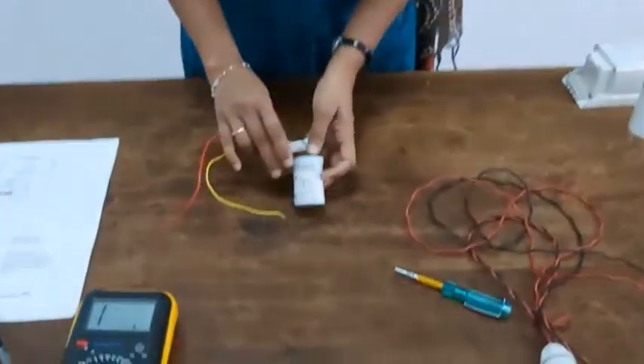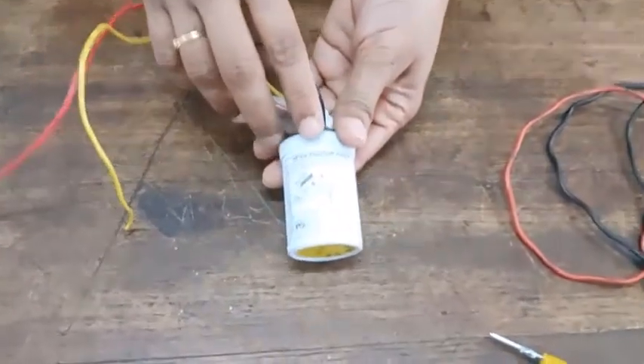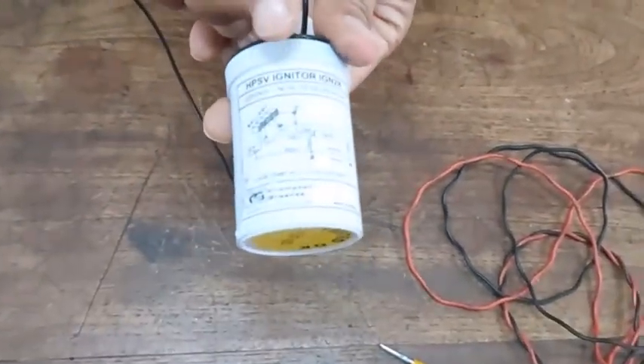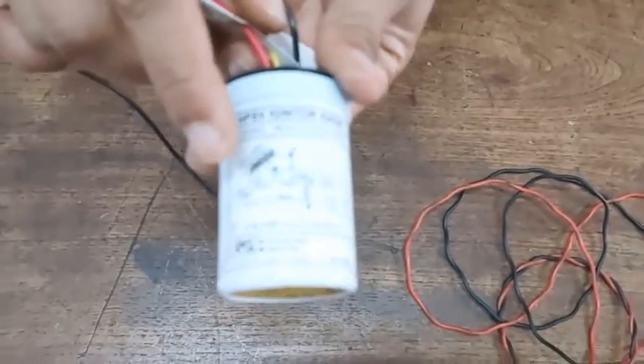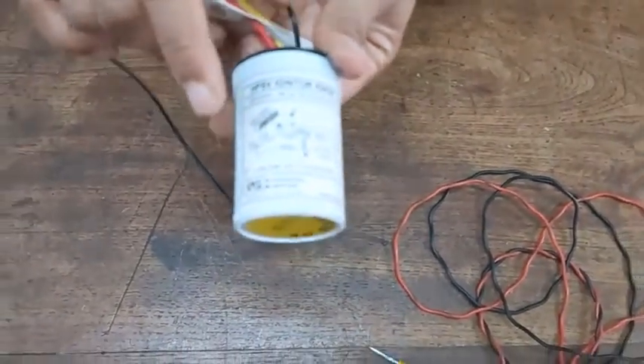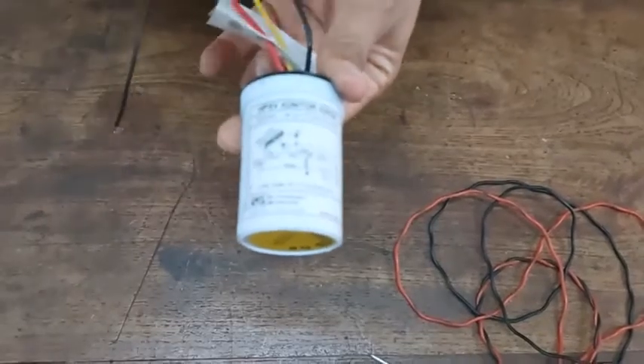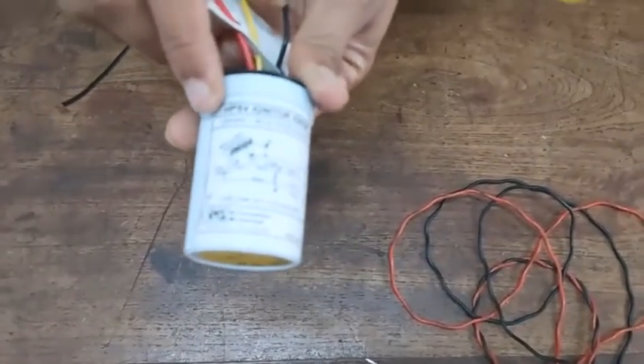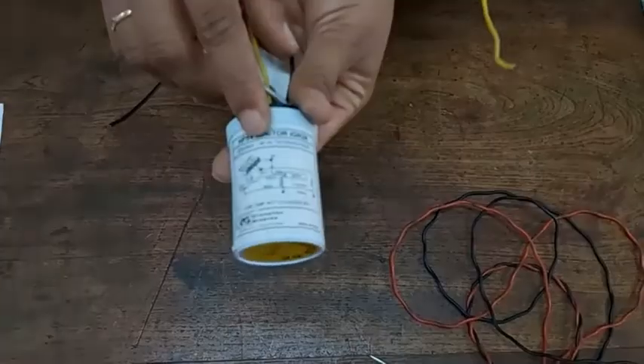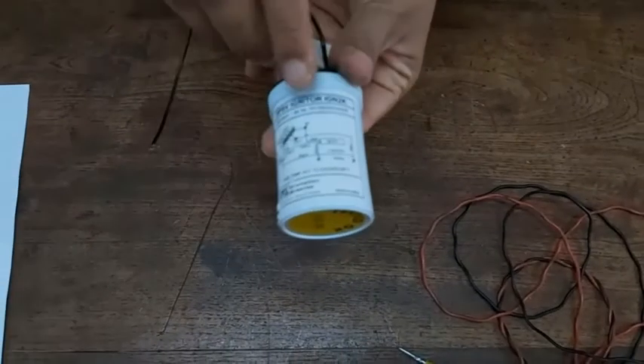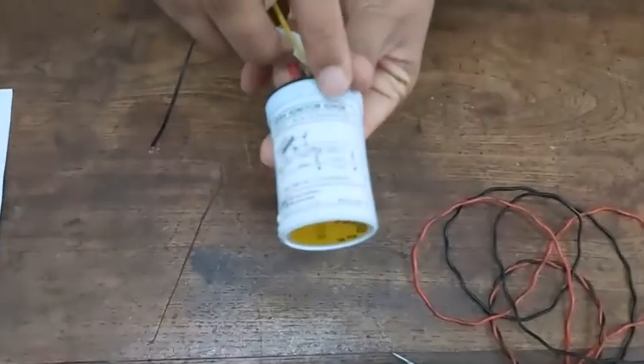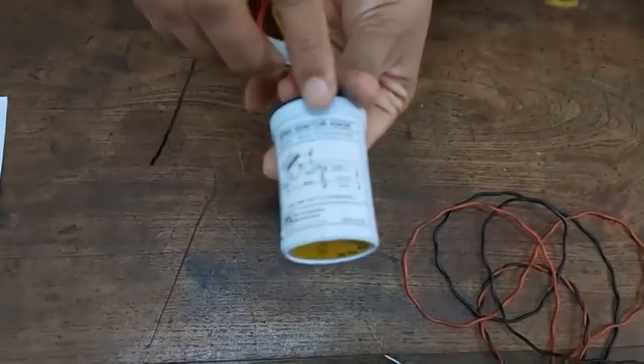This is the igniter of a high pressure sodium vapor lamp set. The specifications of this igniter are provided here. Also the wiring diagram for this circuit is provided here. This igniter is of 220 or 240 volt 50 Hz, and it can be used for a 70, 150, 250 and 400 watt sodium vapor lamp.